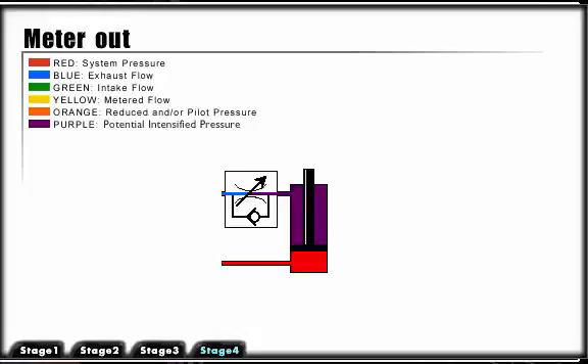When we meter out on the rod side of the cylinder without a load, the pressure is intensified on the rod side. This may damage the rod seals. Meter in or meter out each has advantages and disadvantages, and the application must determine the type of flow control valve placement.